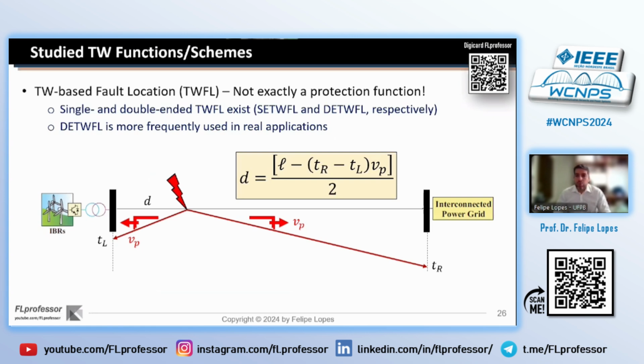So just to explain briefly these functions, traveling wave fault location is not exactly a protection function, but it has been used as an auxiliary function for protection schemes. And the double-ended methodology is the one that has been most frequently used in real applications. Basically, it detects the first wavefront at both line ends and calculates the fault distance using this formula here.